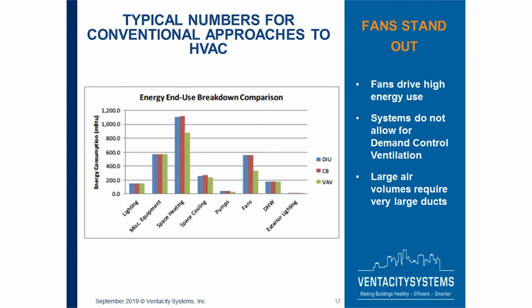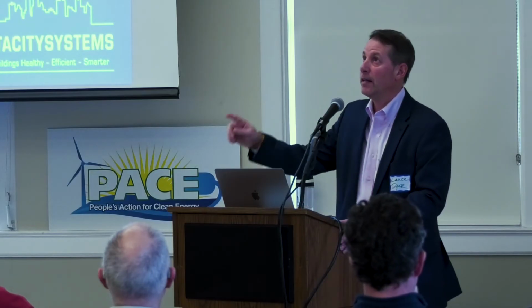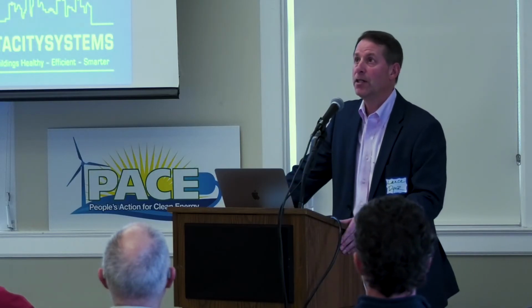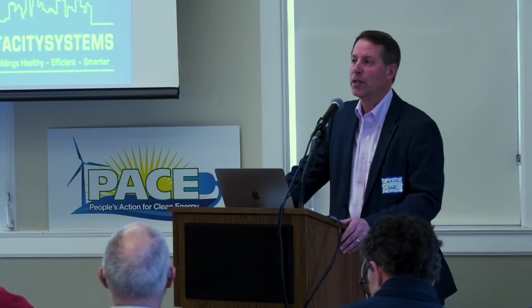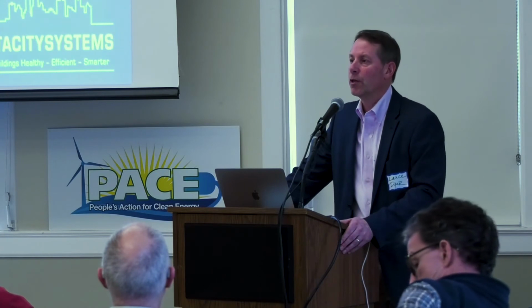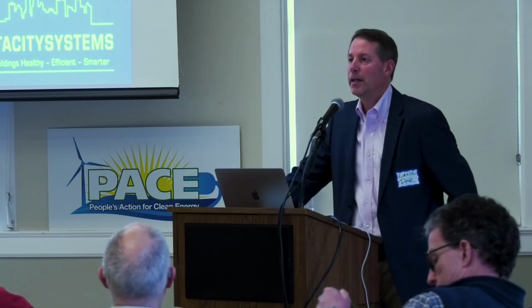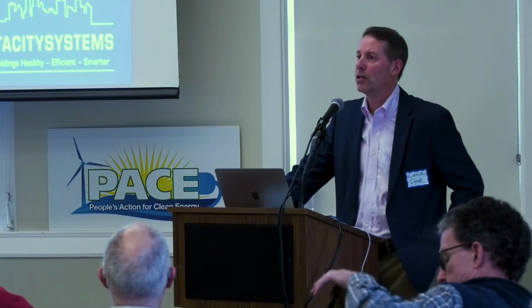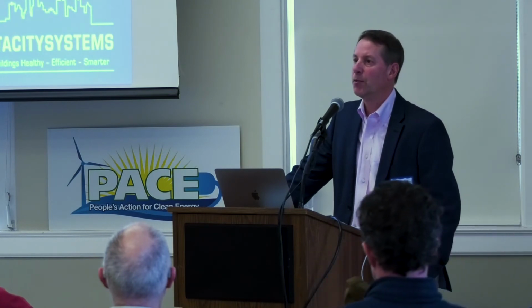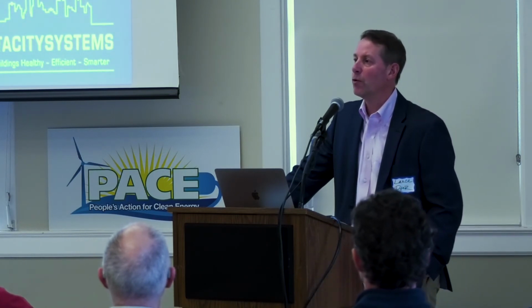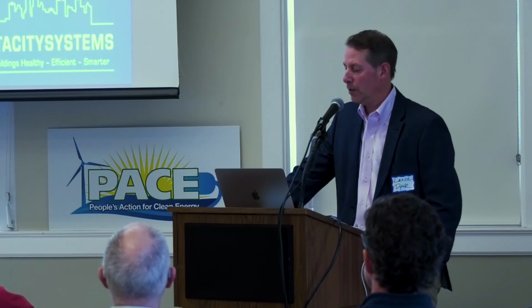The other thing is fan usage. The nice thing about high efficiency ventilation, and also the fans in the HVAC variable refrigerant flow type systems, is that they are all ECM motor technology. So we're converting AC to DC. That power is a lot less than you're going to find with a typical PSC type motor that's on most equipment in our schools.